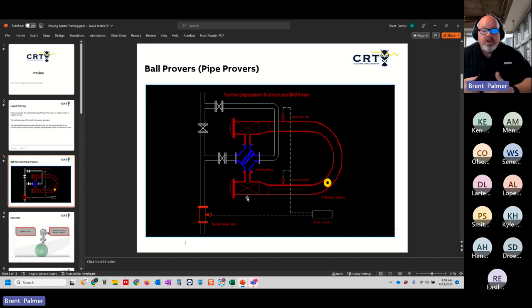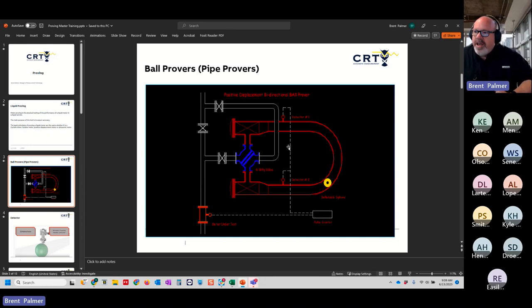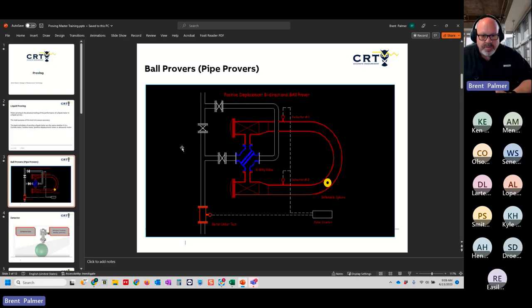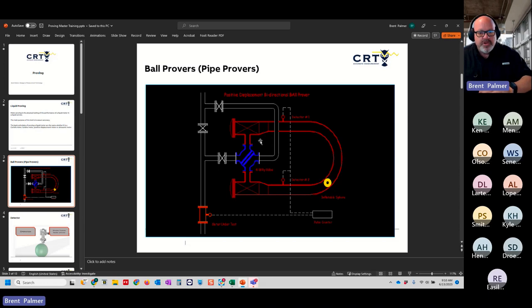If the prover can generate 10,000 pulses from detector to detector, it's a large volume prover; if it can't, it's a small volume prover and additional steps are required. For example, I could have two meters on the same prover: a turbine meter with a K-factor of 2,000 pulses per barrel that reaches over 10,000 pulses, and a helical meter with a K-factor of only 17 pulses per barrel that won't reach 10,000 pulses. The prover is large volume for one meter but small volume for the other, requiring double chronometry and pulse interpolation.